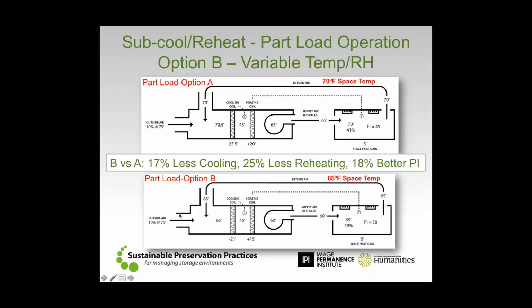Well, now I'm blending 65-degree air with 75-degree outside air, and it means that that cooler mixed air condition equals less work at the cooling coil, less work to achieve the dew point that I'm looking for. Notice we're still doing the same 45-degree dew point.